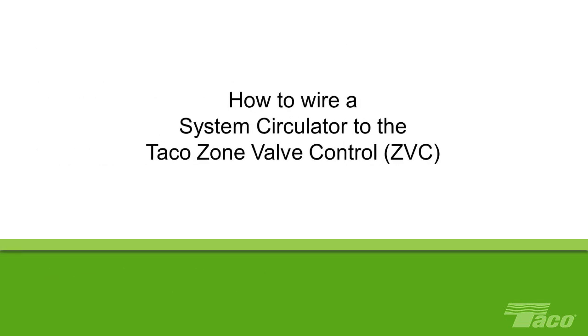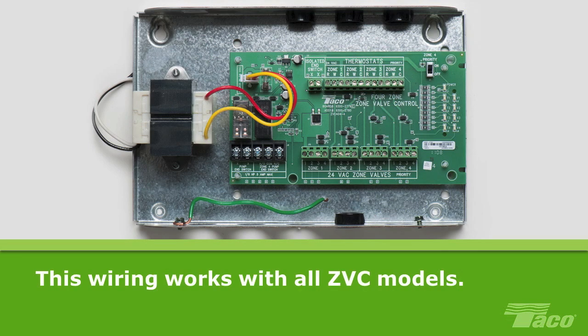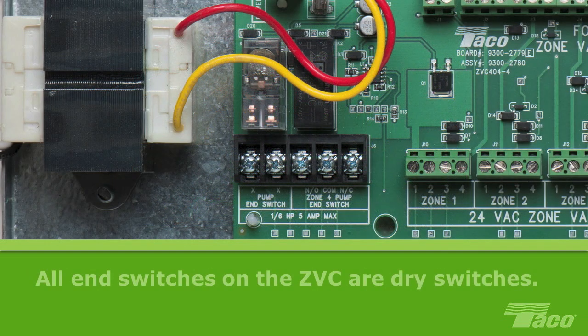How to wire a system circulator to the Taco Zone Valve Control. Today we're using a ZVC 404-4. However, this wiring will also work with all ZVC models. Before starting, please note that all the end switches on the ZVC are dry switches, meaning that there is no power until you energize them with voltage.